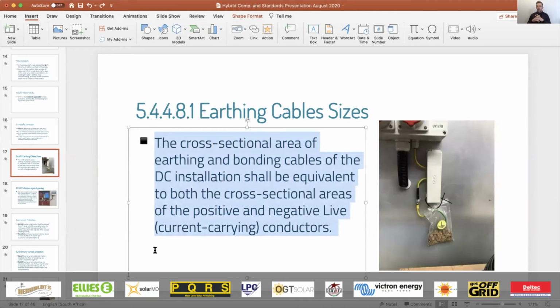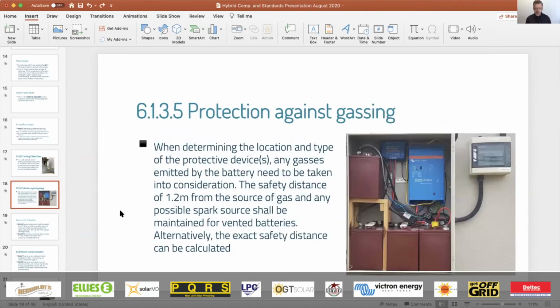And over here, it gives you the cross-sectional area. So getting a lot of questions on the cross-sectional area size of cabling, and this section over here says that it shall be the equivalent to both cross-sectional areas of the positive and negative live conductors. And if you look at the bonding requirements, I think it is a 6 millimeter squared cable is the smallest bonding conductor according to the standards at the moment.